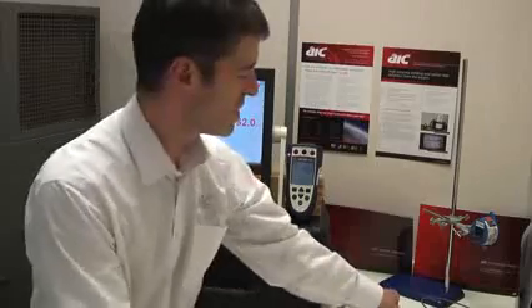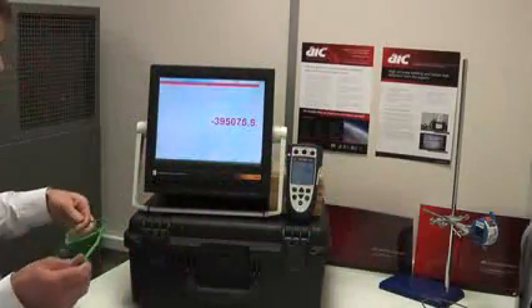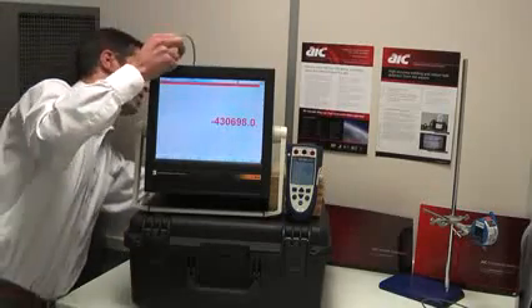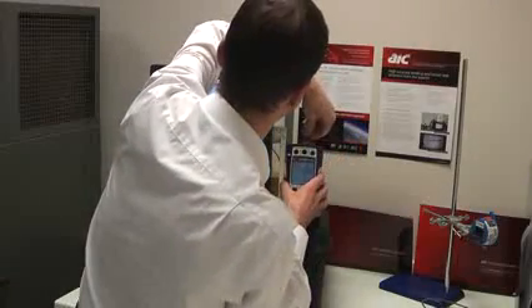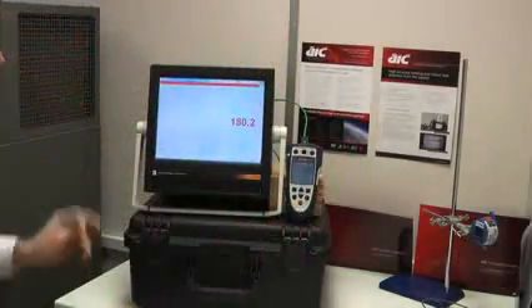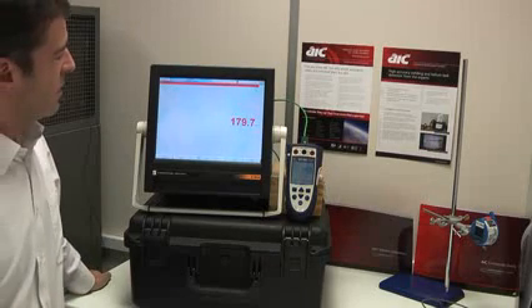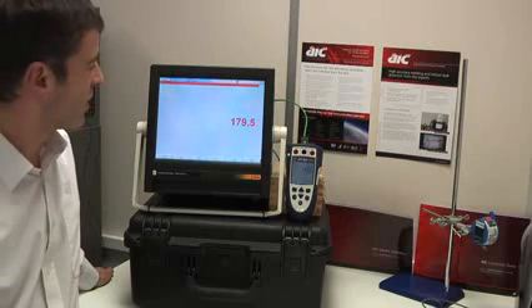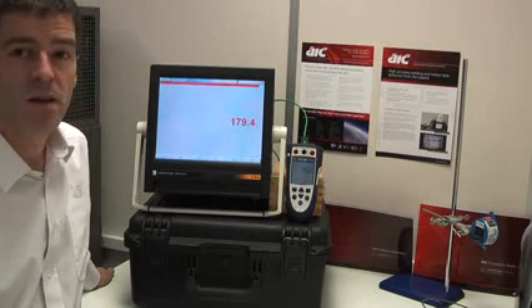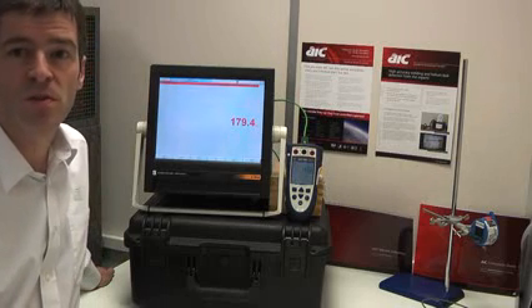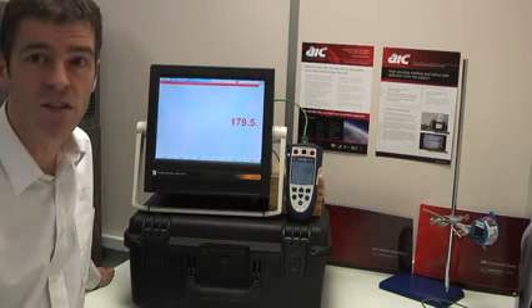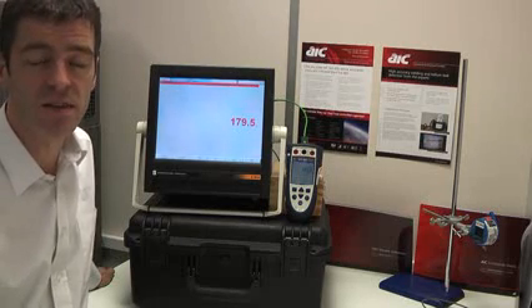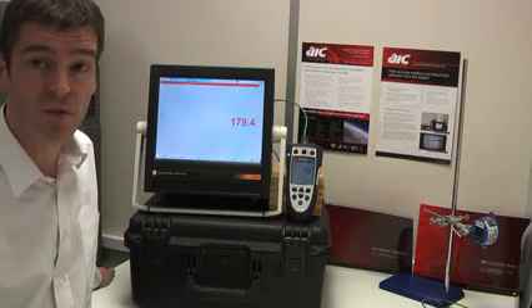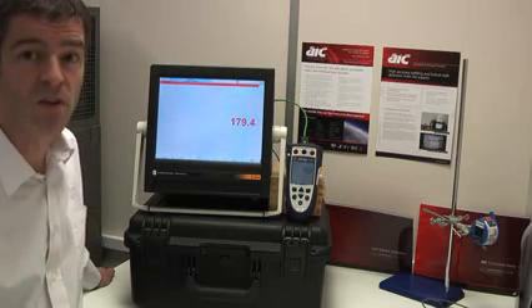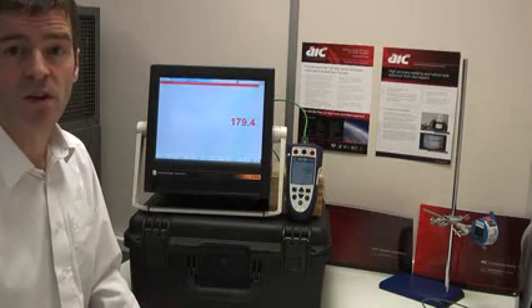Now, the voltage generated by Type K thermocouples at 180 degrees C, as we've got here, ought to be equivalent to 240 degrees Celsius. But in fact we're reading almost exactly the same, 179.54. And this is because the voltage, the signal generated in the thermocouple cable, is generated where there is an area of temperature gradient. So anywhere that experiences a temperature gradient will experience a voltage. Simply passing a voltage down it from our process calibrator makes no difference to the character of the cable.